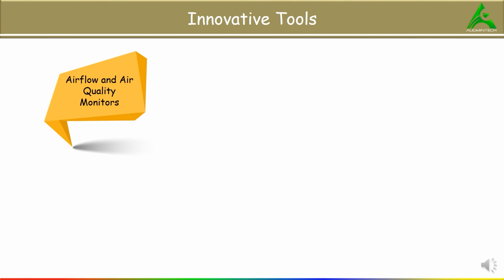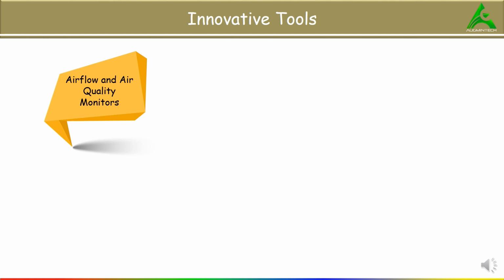Next are airflow and air quality monitors. These tools measure airflow, humidity and air quality parameters to ensure HVAC systems provide a comfortable and healthy environment. For example, the Testo 440 air velocity and IAQ meter measures CO2, temperature, humidity and air velocity with interchangeable probes. Used in hospitals, this type of monitor verifies that the HVAC system meets indoor air quality standards, ensuring patient safety.